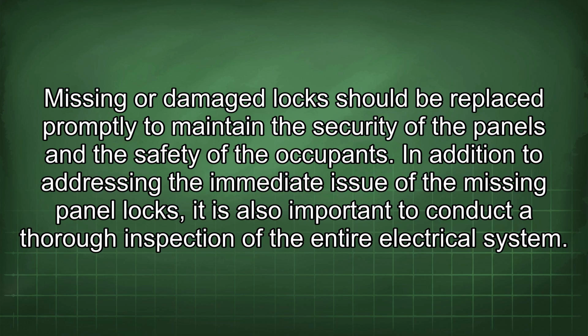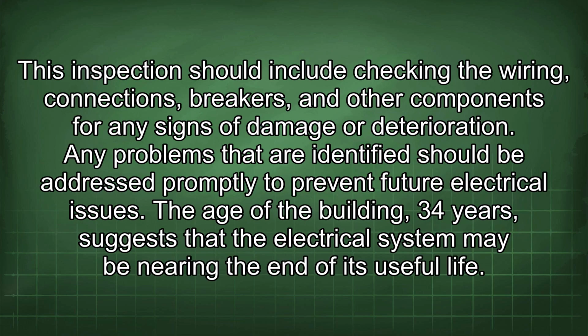In addition to addressing the immediate issue of the missing panel locks, it is also important to conduct a thorough inspection of the entire electrical system. This inspection should include checking the wiring, connections, breakers, and other components for any signs of damage or deterioration. Any problems that are identified should be addressed promptly to prevent future electrical issues.